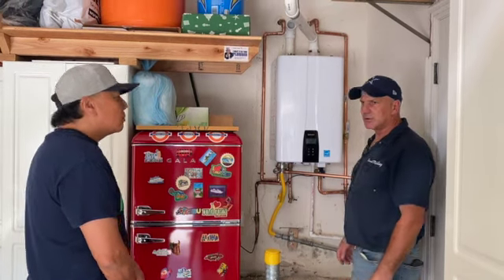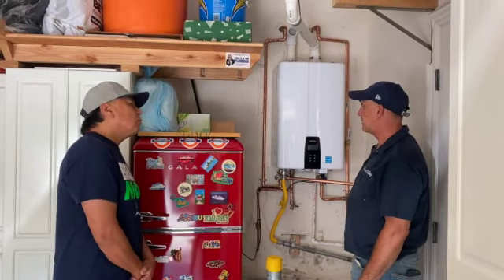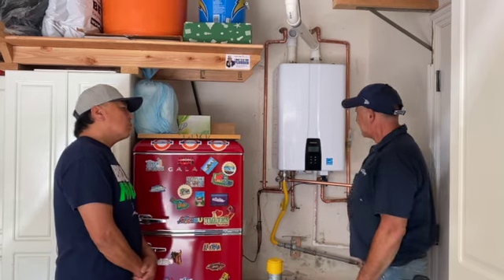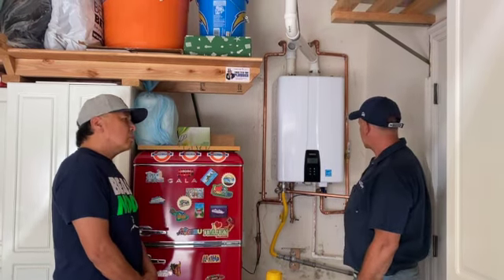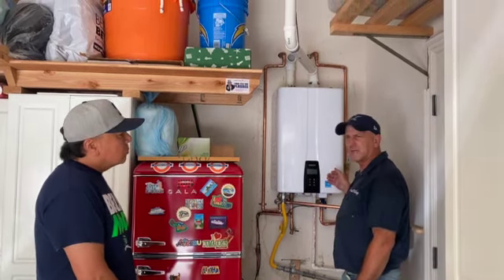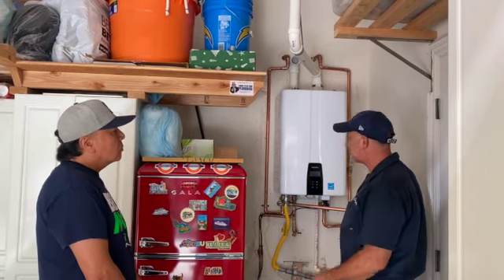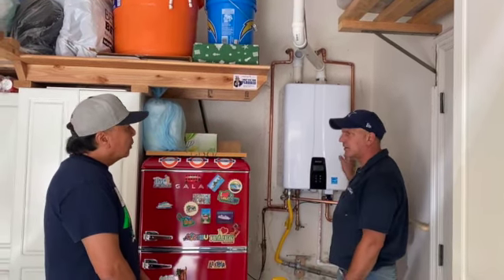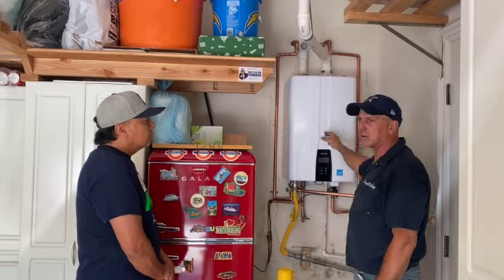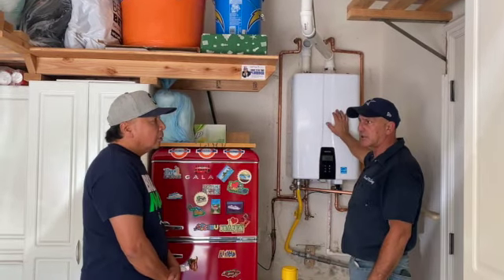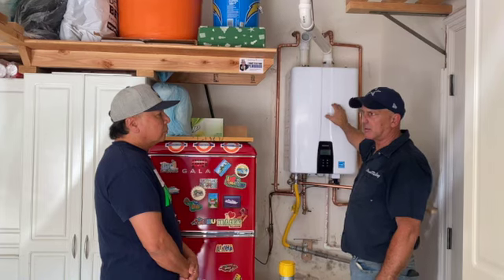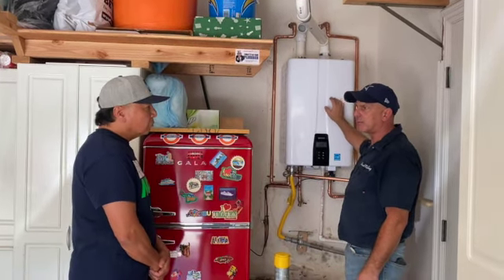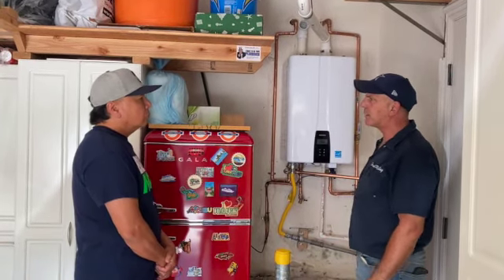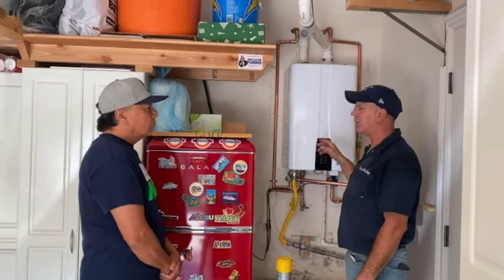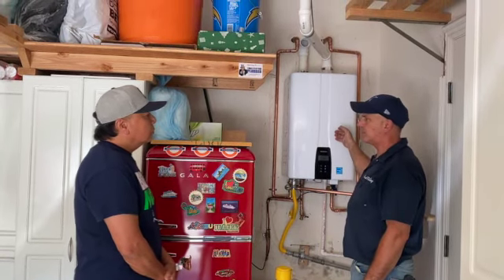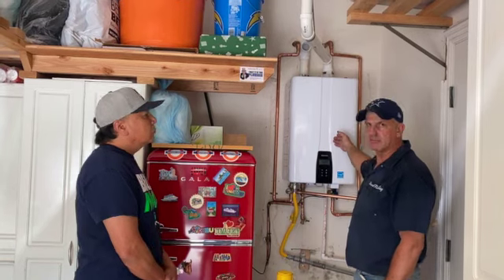It's done with a solution - we usually use a distilled grade white vinegar solution, pumped through here, usually about 5 gallons for about 45 minutes, once a year, to make sure the heat exchanger stays nice and clean internally. This particular heat exchanger is a stainless steel 15-year warranted heat exchanger from the manufacturer, but it is required to keep it up to code and to keep your warranty valid - you have to flush it once a year.